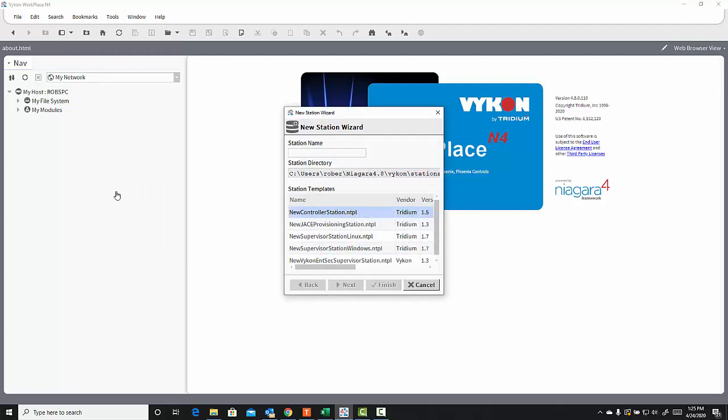When I do that, I can select a name for my station, and I can choose a template. Now, there are several default templates depending on how you're going to deploy the station, either into a JACE or into a supervisor, and there's also the option to create your own templates, so that if you know certain features that you want to put in every one of your stations going forward, you can create a template that's customized, and you can select it from this list. I'm just going to use a standard new controller station template.